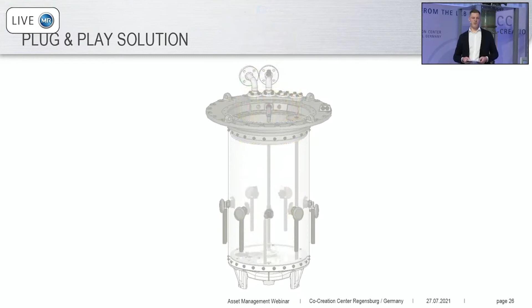What you see in this animation is more or less happening in real life. Of course, there is a drive shaft arrangement connected in the tap changer, but it is more or less a plug-and-play solution. There is no modification work necessary on or in the oil compartment. No other modification is necessary on the tap changer. We deliver this diverter switch insert for this tap changer ready for operation, means dried and tested, HV tested, and ready for installation.